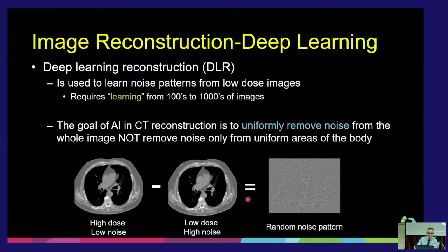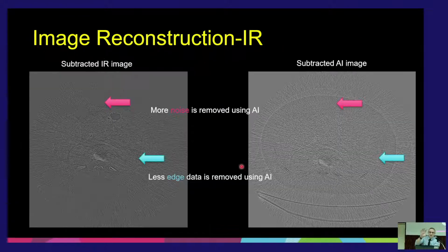And so here we go. What we end up doing is they fed thousands of images of rather high dose, low noise images into an algorithm, and low dose, high noise images. Same patient, just acquired in different ways. There are lots of different algorithms and techniques, and there's an hour-long talk we could give on just this one step. But basically, the system learned that the difference between these high and low dose noise images was largely just stochastic noise. So once it learns what the noise patterns are, you can simply apply this algorithm to remove noise instead of needing to use that regularization function.